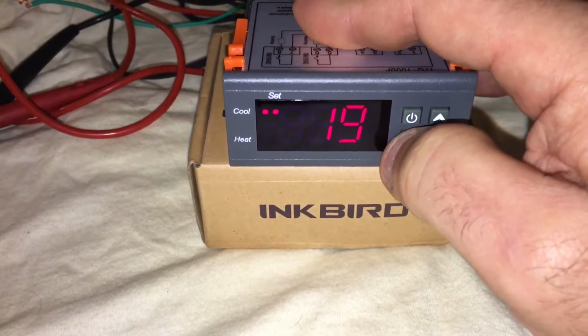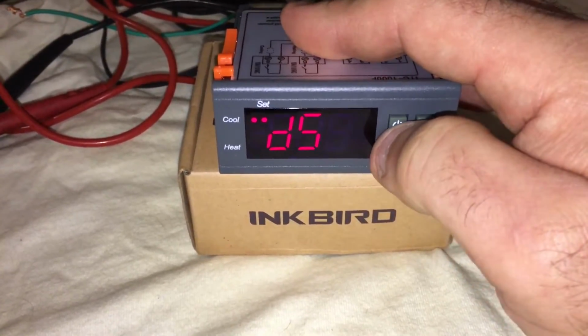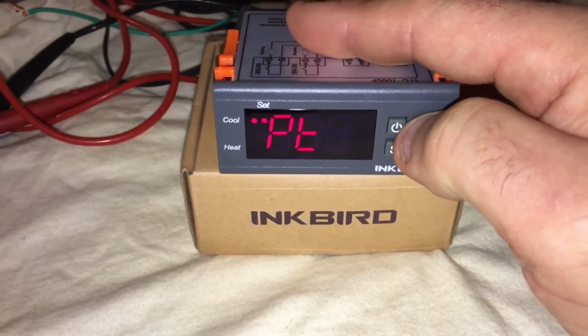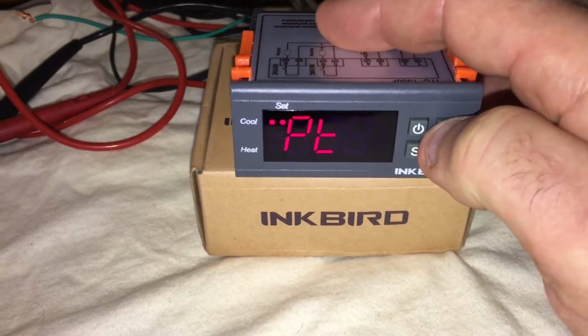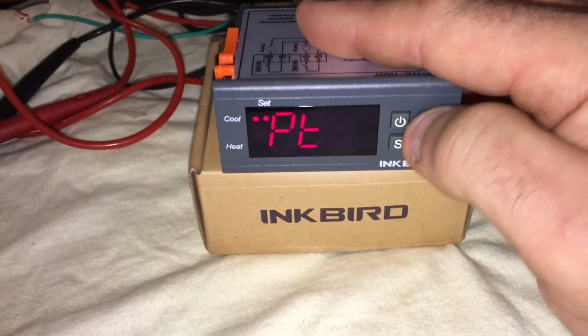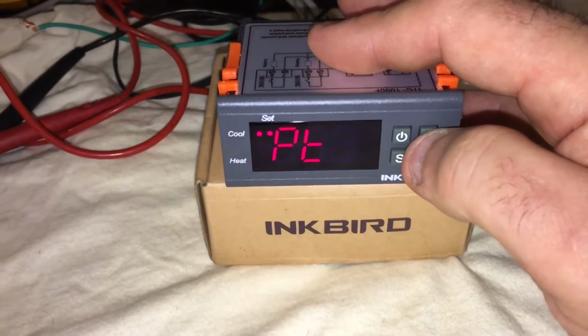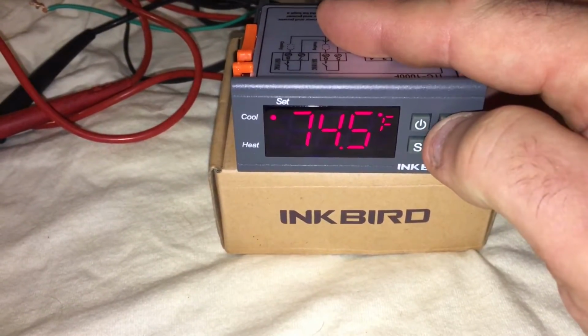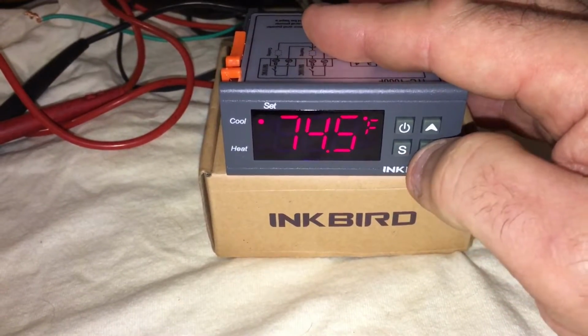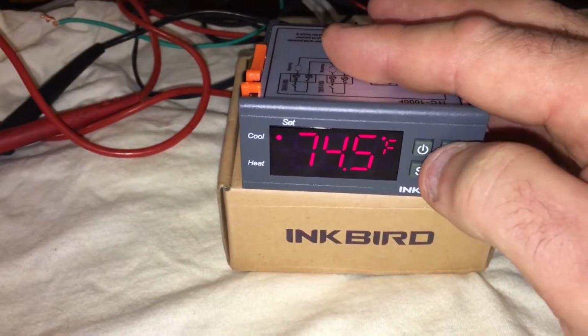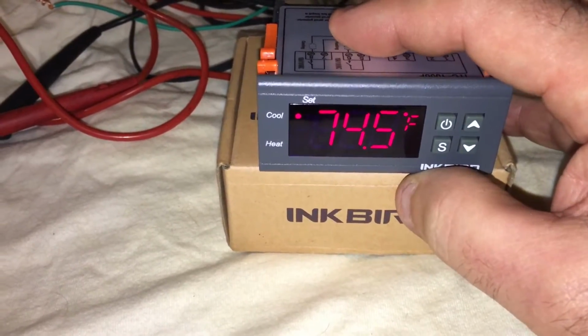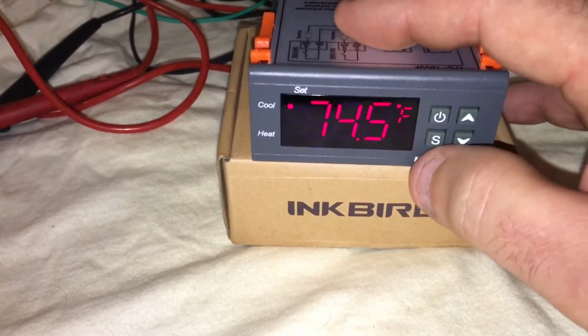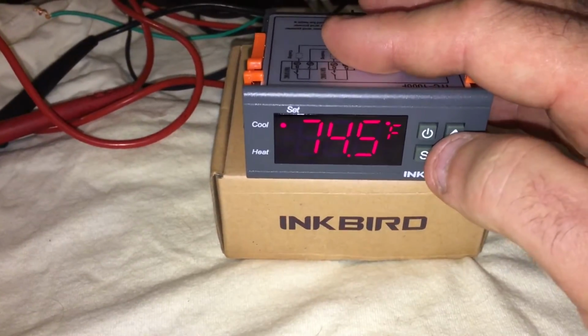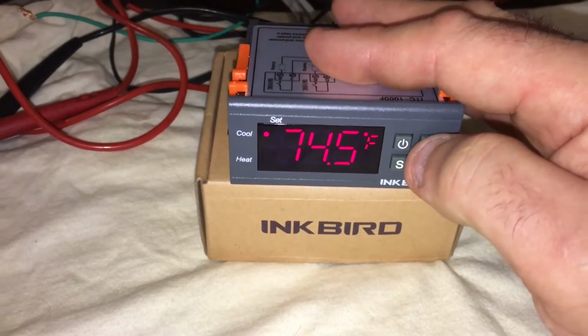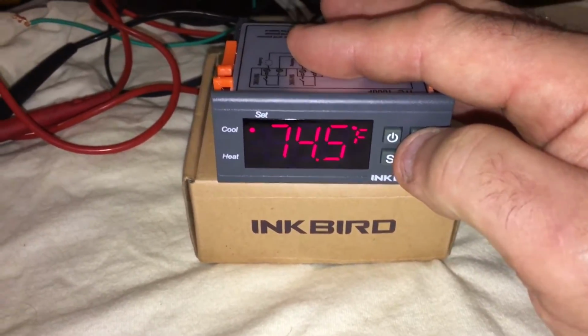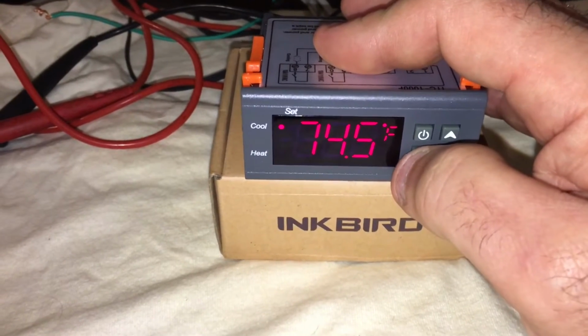That means it'll come back on at 39, which will give the evaporator some air defrost time, because it'll be above 32 degrees. It'll start air defrosting at 33 degrees, so that would be 7 degrees above freezing - that should give it lots of time to air defrost. There'll probably end up being a 10 or 15 minute evaporator air defrost every cycle. So that's why that works good.